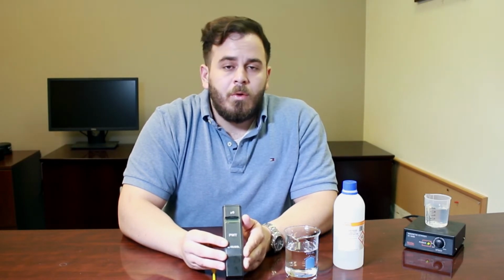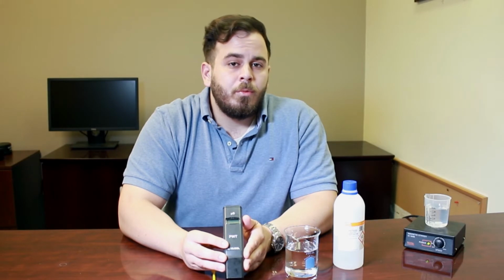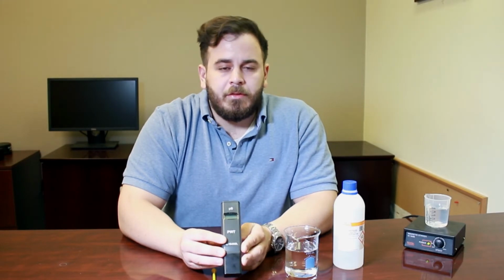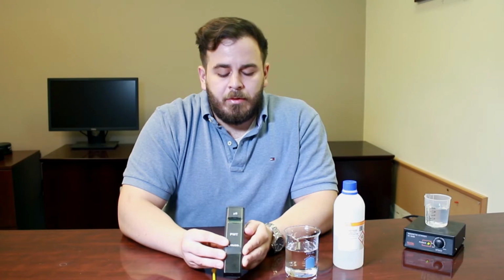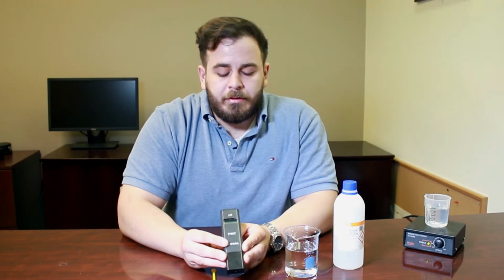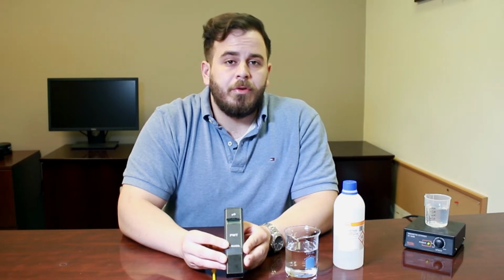So it necessarily won't pick up all the particles that are dissolved in the water. It's just going to be picking up particles with an electrical charge attached to them, or something with an ionic strength to it, so things like chloride and sodium, or phosphates. So it's not going to pick up everything, but it's going to pick up most things in the water. So it's generally considered a good way to measure water purity.